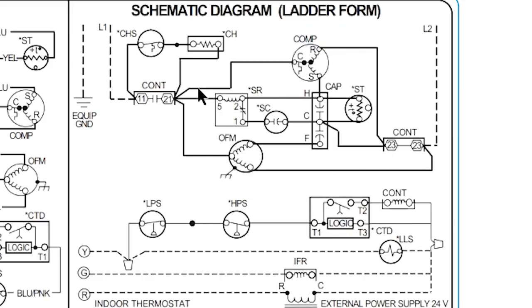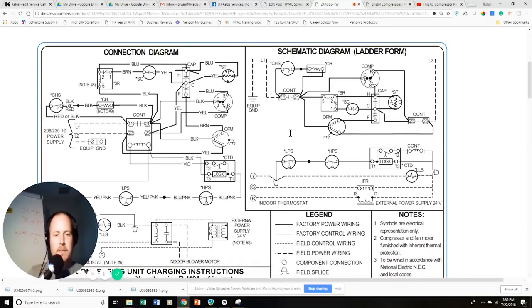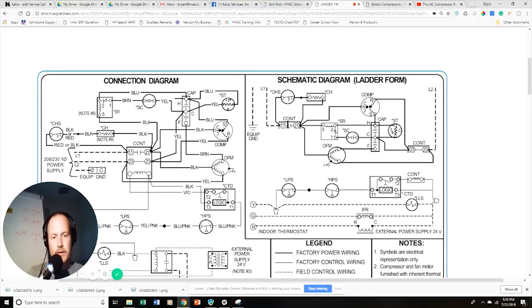The connection diagram and schematic diagram show the same thing in slightly different ways. On the schematic side, everything is broken up to make diagnosis easier. On the connection diagram side, components are grouped together so they're easier to identify — the contactor looks more like an actual contactor. Now, going through this contactor: this is a normally open contact. You can tell because there's a gap between the two contact points.